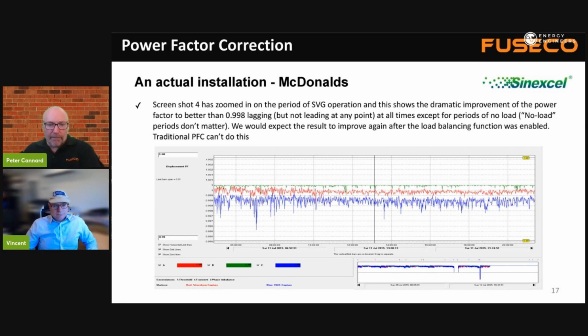These are the three phases. We also have functions on the power factor correction unit to help balance these phases as well. I think my colleague Dave made a note that load balancing wasn't included in this shot, but you can also balance the phases. And you don't need the power factor correction unit going flat out to get close to 1—you might have a target of 0.95, for example, and that'll save a little bit of the energy used by the filter itself in bringing it to these high performance values.